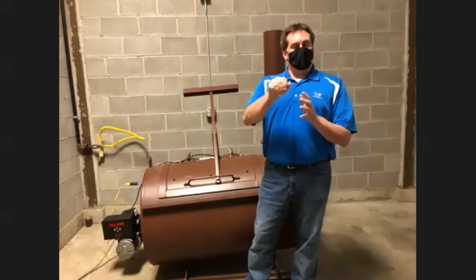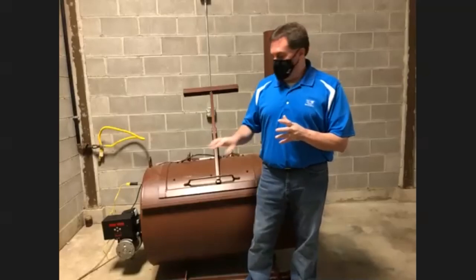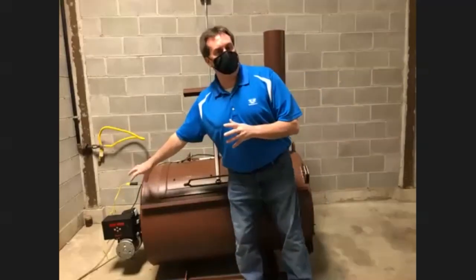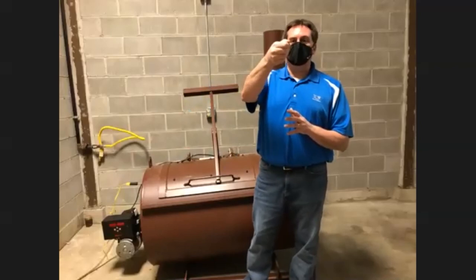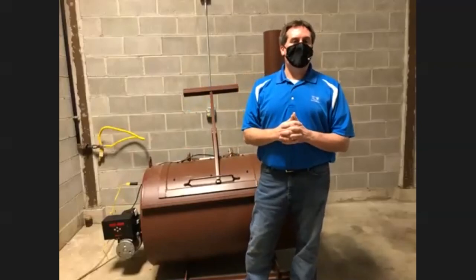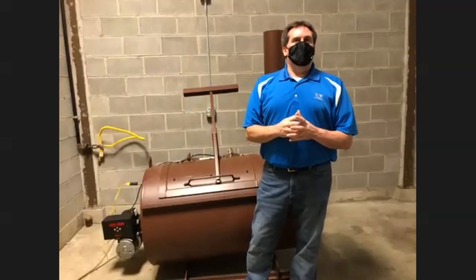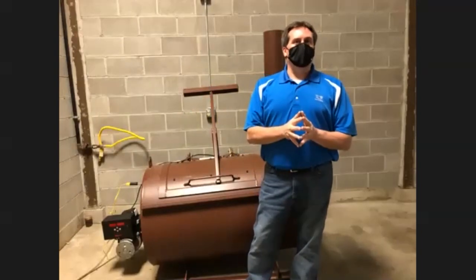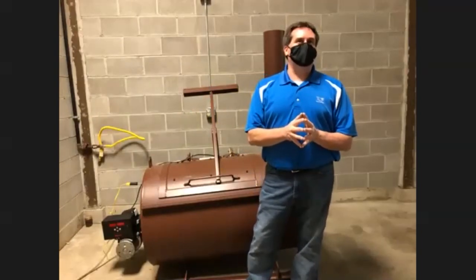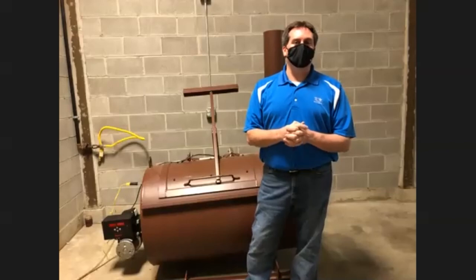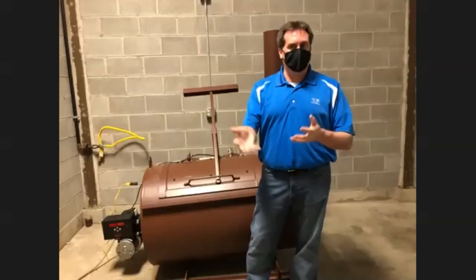All afterburner controls will have a mechanical timer, and all the main controls will have electronic control to it. So on an afterburner, secondary burner, you have a mechanical timer. And if you're having a reset issue on the motor, you could test the reset. You can do continuity tests on them. If it's failed, there's really not much more to do. You might have to replace the motor itself.